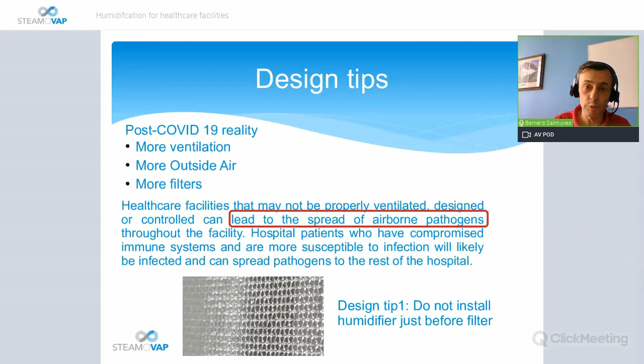So if you put more filters, make sure that you don't put the filters right after a humidifier, a steam humidifier, or an atomizer. Because the filter will catch the unabsorbed steam or any droplets in suspension, and you will clog the filter. Second, you have a high risk of contamination of the filter due to this. So when people want to put more filters, tell them to verify where they will put them: never downstream, or too close if they are downstream, but upstream of the steam humidifier.